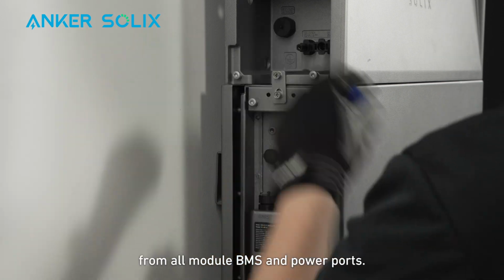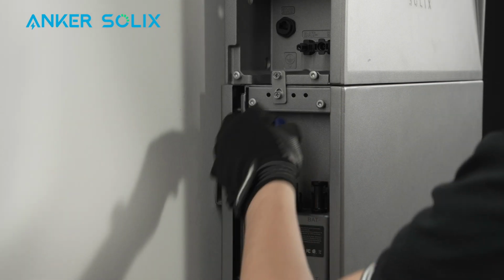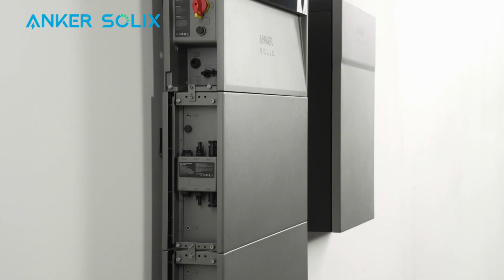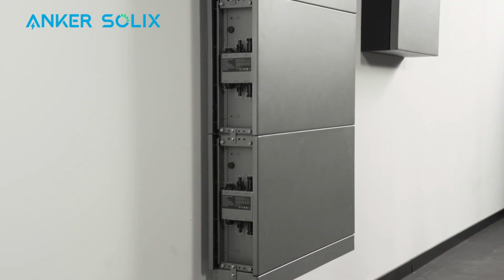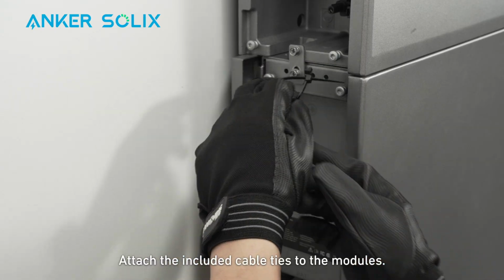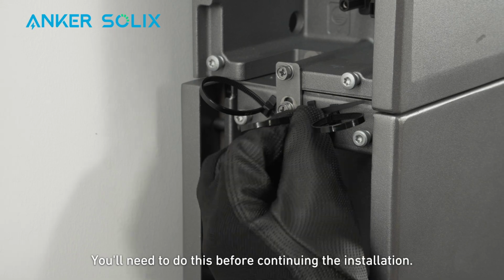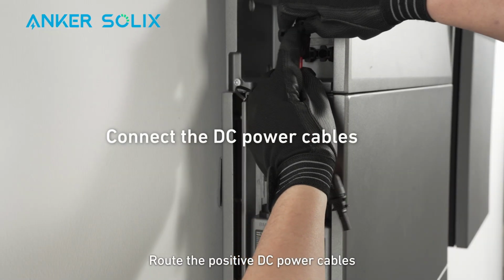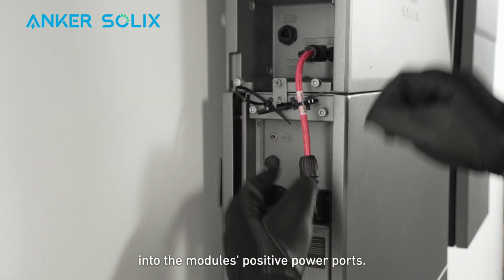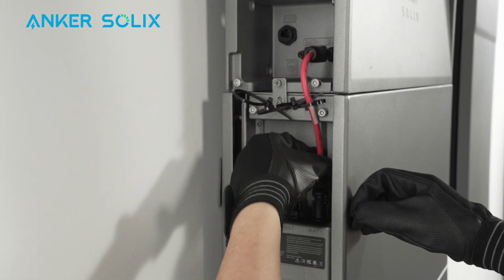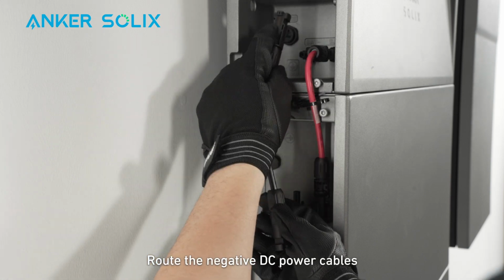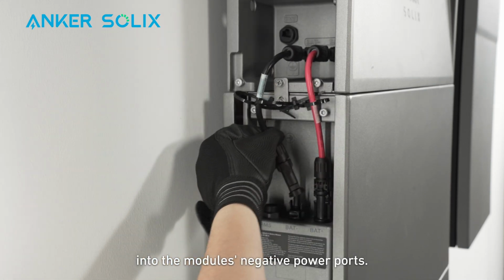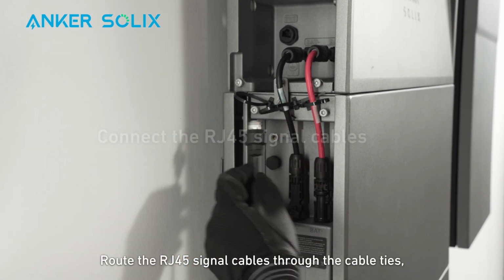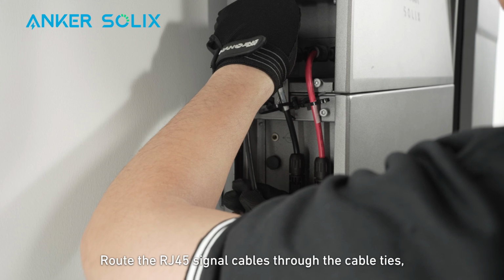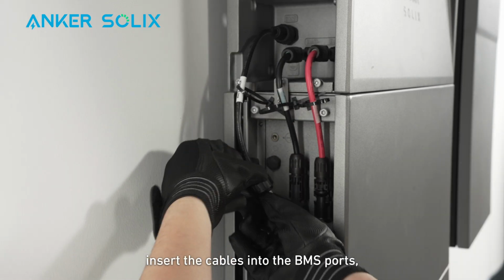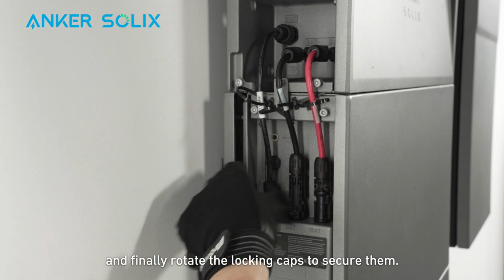Remove the dust-proof plugs from all module BMS and power ports. Attach the included cable ties to the modules. You'll need to do this before continuing the installation. Route the positive DC power cables through the cable ties and insert the cables into the module's positive power ports. Route the negative DC power cables through the cable ties and insert the cables into the module's negative power ports. Route the RJ45 signal cables through the cable ties. Loosen the locking caps, insert the cables into the BMS ports, and finally rotate the locking caps to secure them.